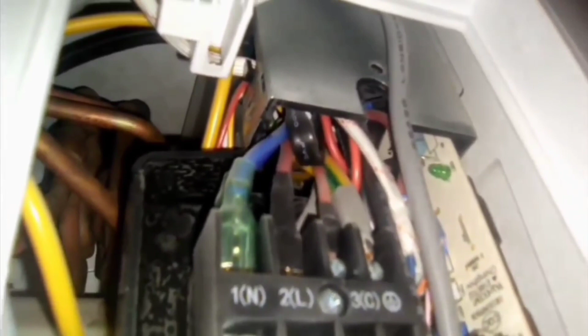First we will turn on the unit and check the LED condition. If this LED is on or off, it means the indoor PCB is faulty — it should always be flashing. Here you can see, we have turned the unit on and the indoor PCB's LED is not flashing, which means our indoor PCB is faulty.